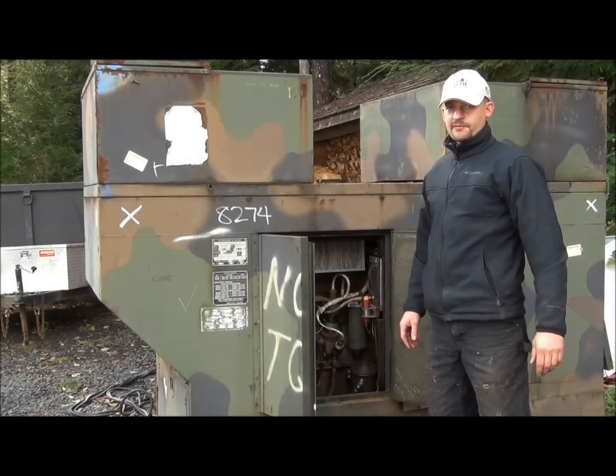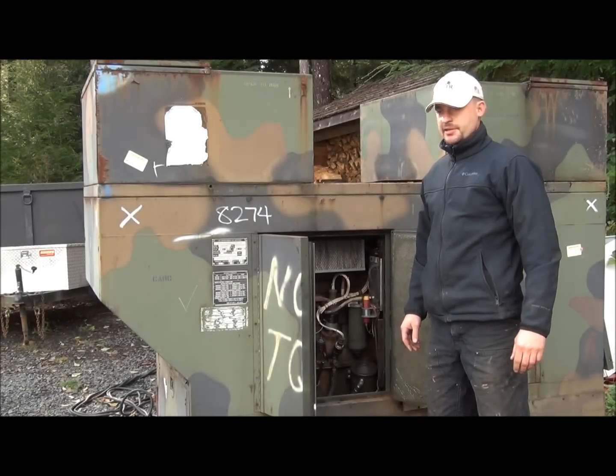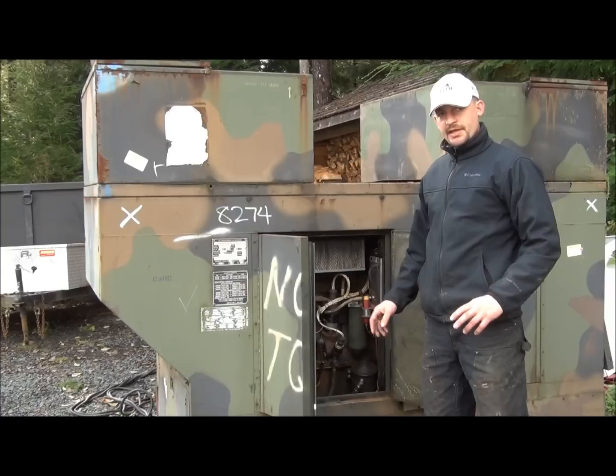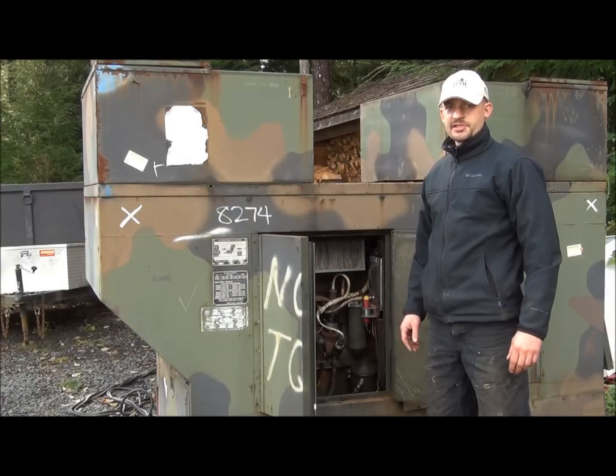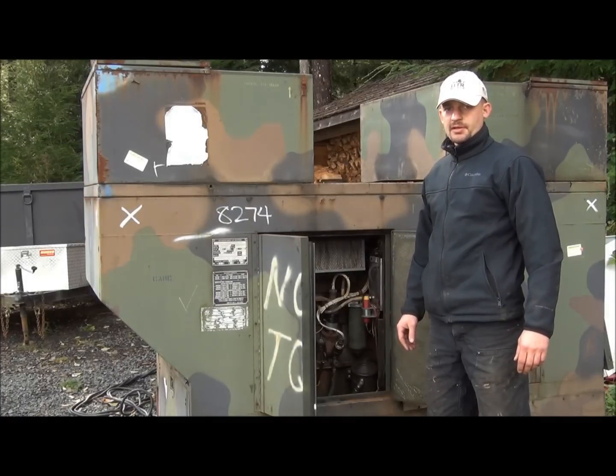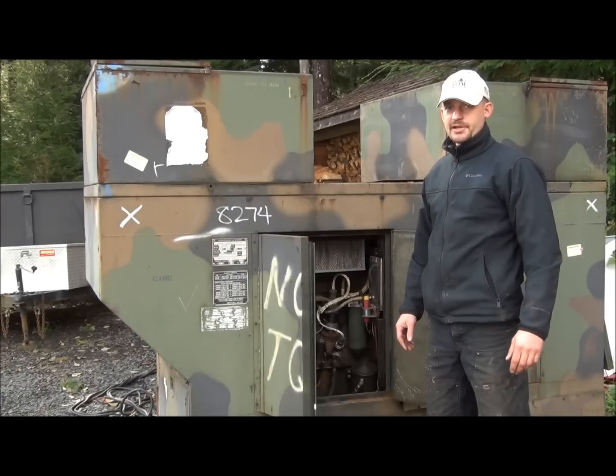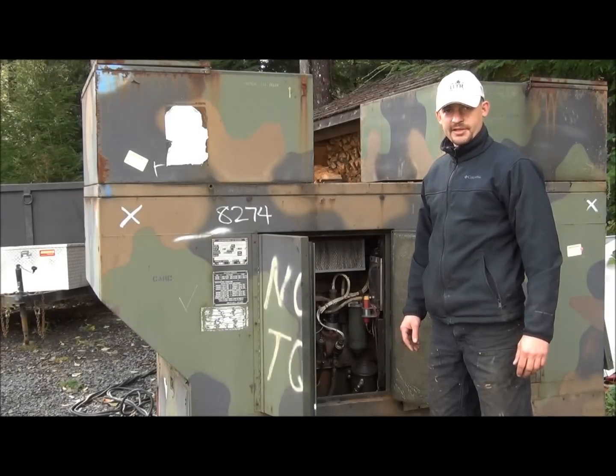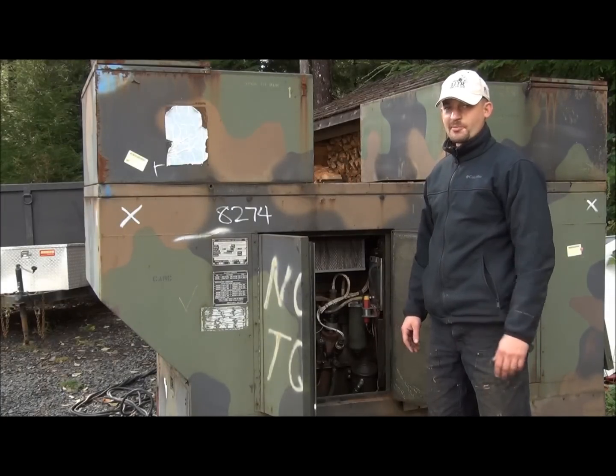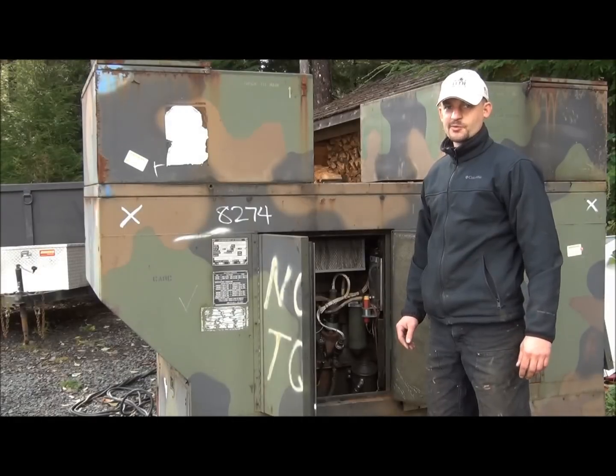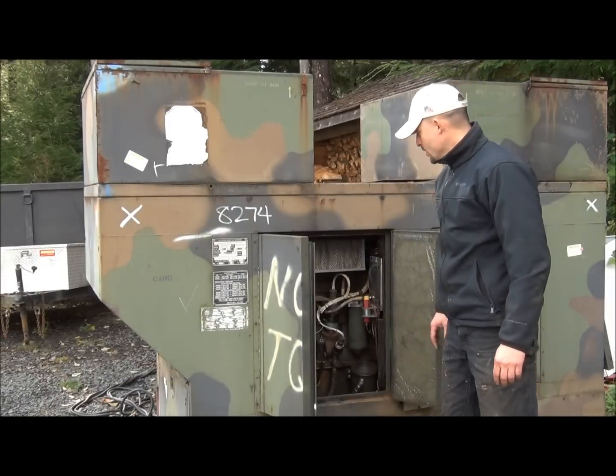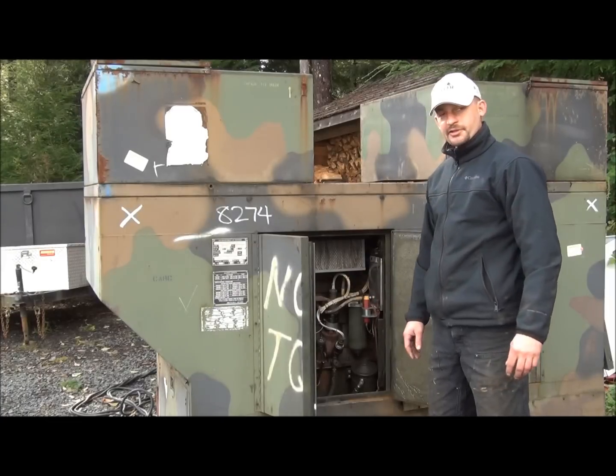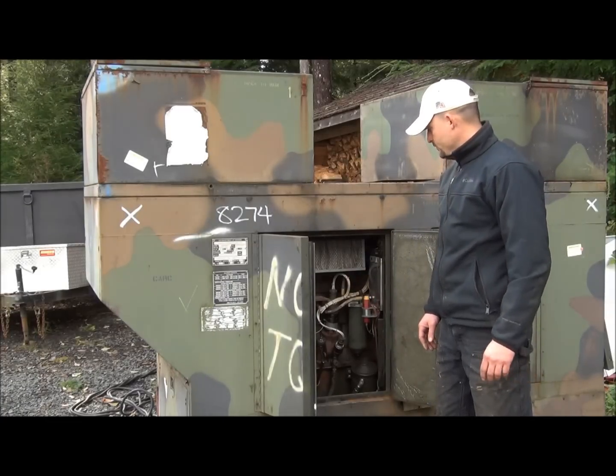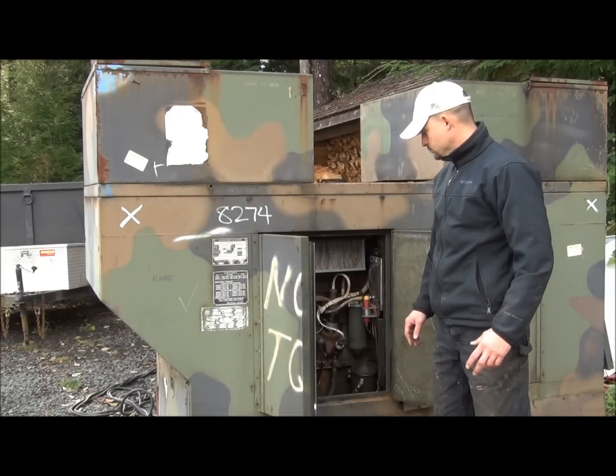Alright, I've had the engine running for probably 15 to 20 minutes now, and I went ahead and checked all the gauges. Everything looked normal. The thermostat definitely opened, and temperature was in the normal operating range. I didn't see anything abnormal on any of the gauges. Even the voltage was proper, right at 208 volts and about 120 volts for each individual line. I walked around the generator and took a look at everything inside, and I don't see anything out of the ordinary. Everything appears to be tight.